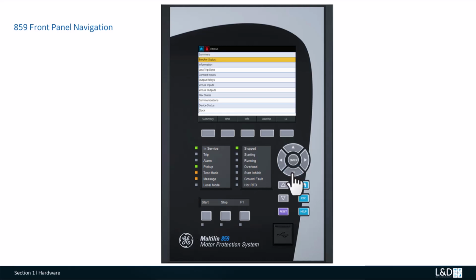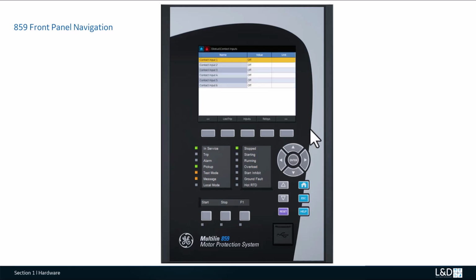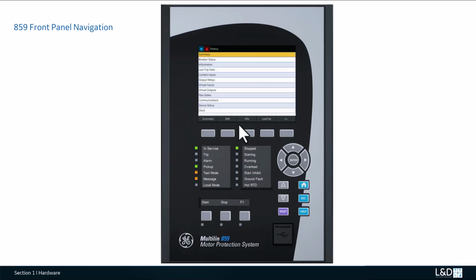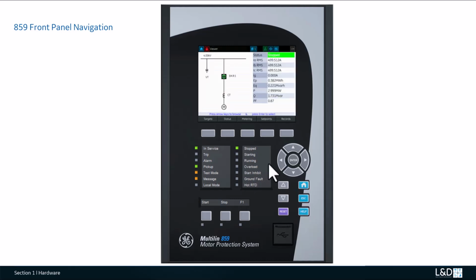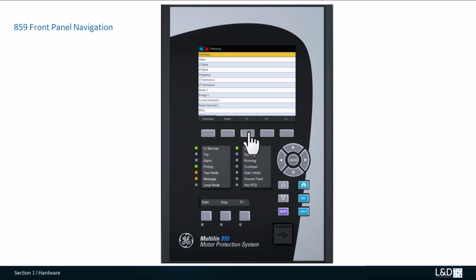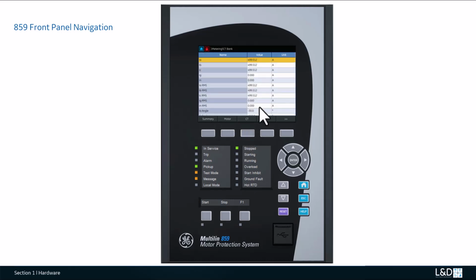So for example, if I want to check the contact inputs, I just click the down arrow key until the contact inputs is highlighted, then press the enter key. Then from the software, we can see the updated contact inputs: contact inputs 1 to 6 status is off. So we can escape from this one and check all the other status information. Then we can further escape to the main menu. Under the metering, we can check the metered values. Actually, we already see some metering values here, but from here we can see more metering under the CT and VT. So this is for the three-phase current and voltage.